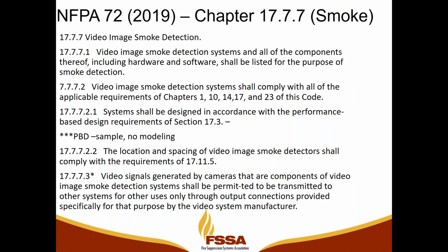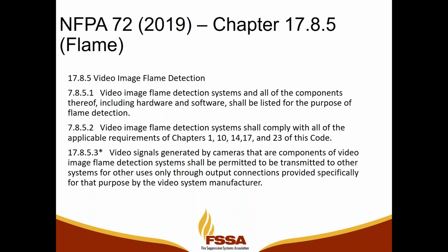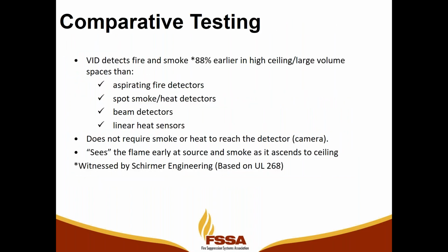NFPA 72 does discuss video image smoke detection and video image flame detection. The standards are very simple, very similar to the requirements of other detectors: communication, backup power, etc. In NFPA 72, there is a recommendation of a performance-based design that does not have to include modeling.